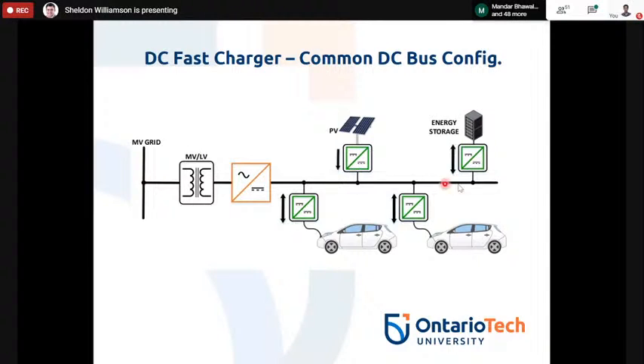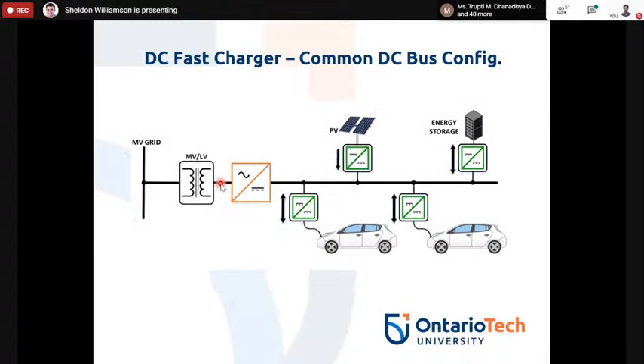Then you have the common DC bus, or DC microgrid. Here we remove the inverter from each stage, all those orange blocks, and instead place one central inverter in front of the transformer, with several DC-DC converters connected to the DC grid—a very simple solution.